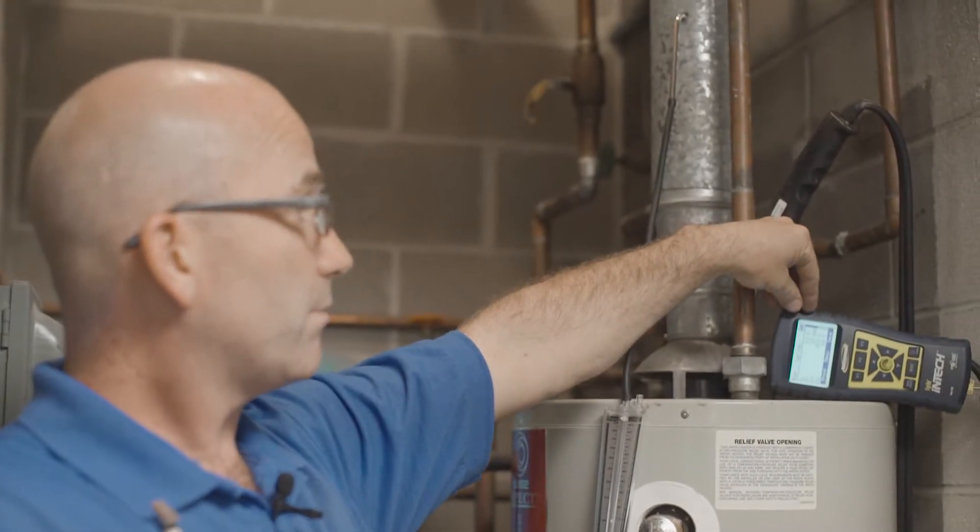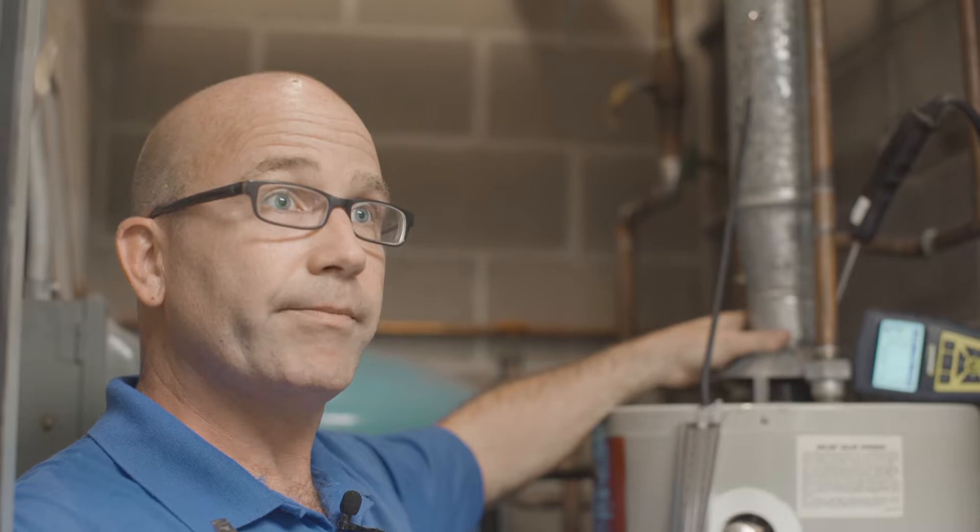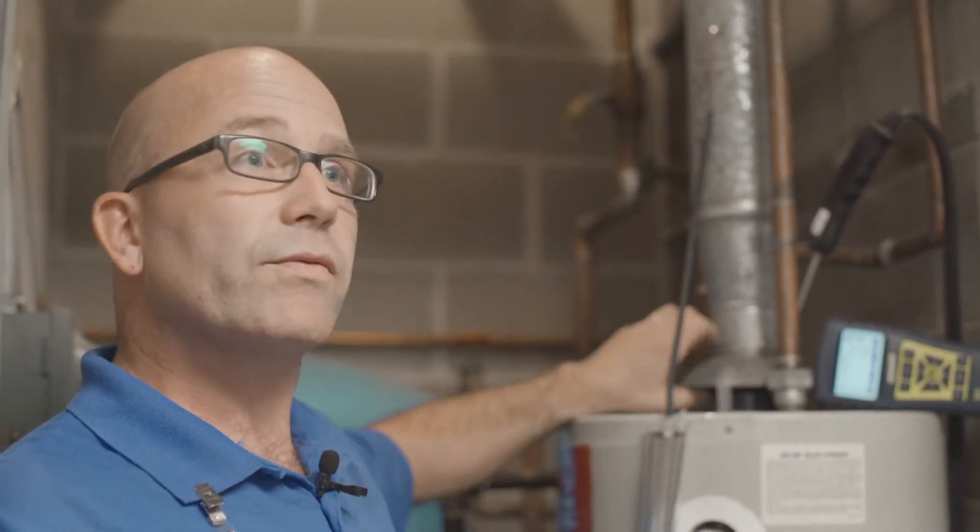Now if this number were at 3, 4, or 500 parts per million and it wasn't drafting at the same time, then that's going to have a negative effect on anyone that's in the home because that 3 or 400 parts per million could cause someone to get sick.